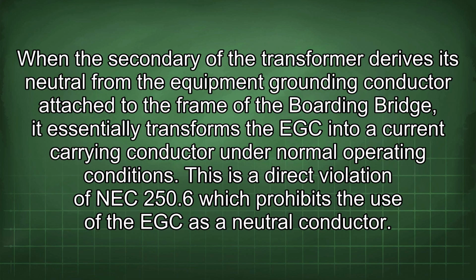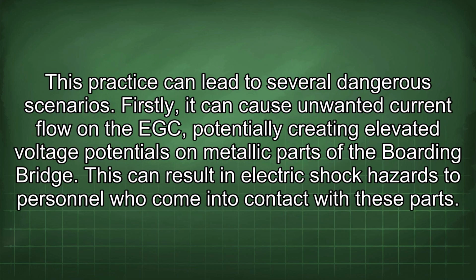When the secondary of the transformer derives its neutral from the equipment grounding conductor attached to the frame of the boarding bridge, it essentially transforms the EGC into a current carrying conductor under normal operating conditions. This is a direct violation of NEC 250.6, which prohibits the use of the EGC as a neutral conductor. This practice can lead to several dangerous scenarios. Firstly, it can cause unwanted current flow on the EGC, potentially creating elevated voltage potentials on metallic parts of the boarding bridge. This can result in electric shock hazards to personnel who come into contact with these parts.